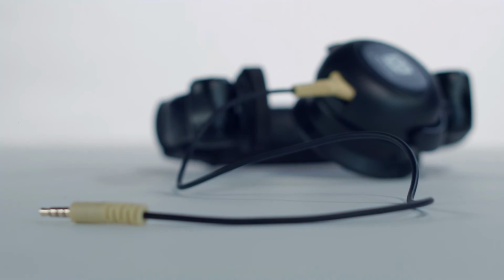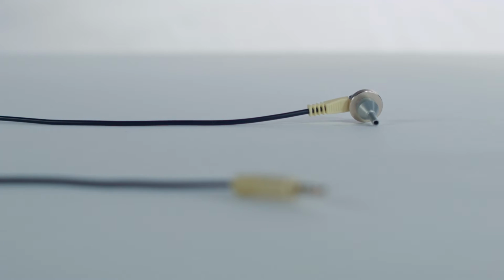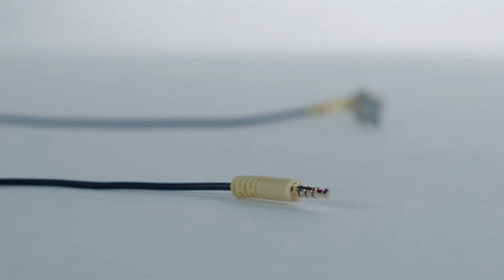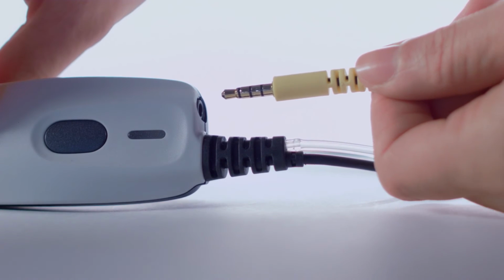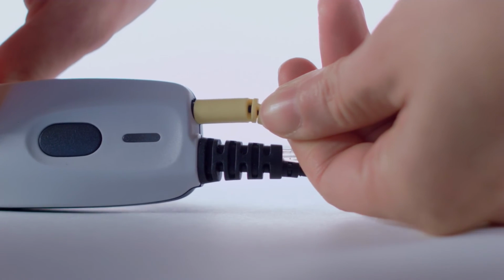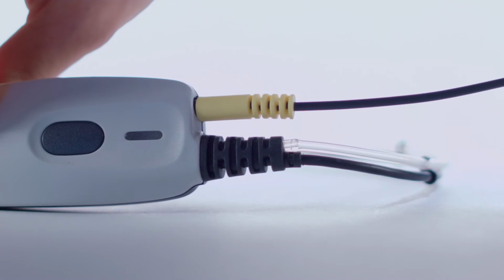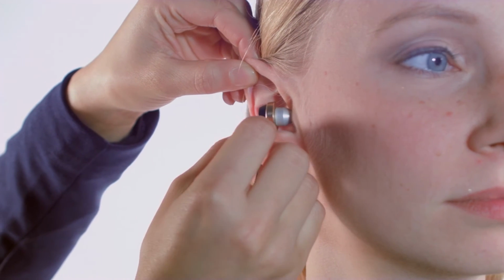A contralateral acoustic reflex measurement can also be performed with the diagnostic probe. The contralateral phone included is specific to the region purchased. Attach the contralateral phone in the jack labeled Contra on the shoulder box. Place the contralateral phone gently in the ear or on the head of the patient, depending on the configuration.